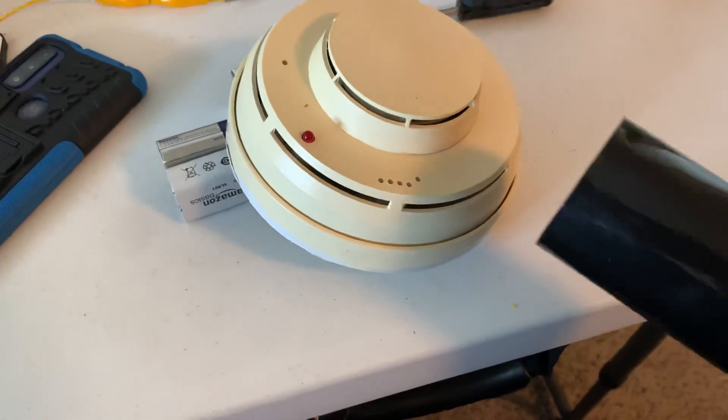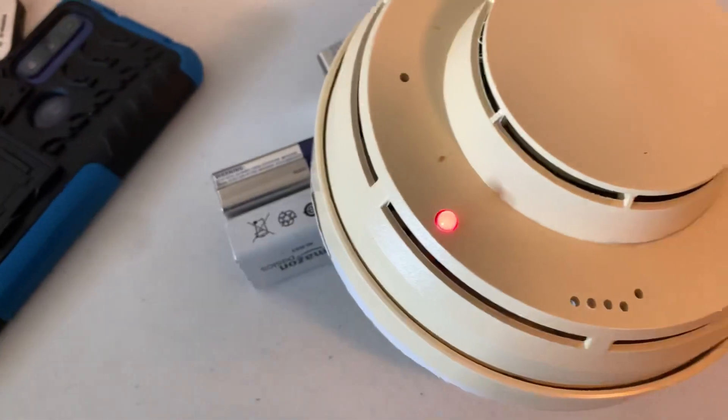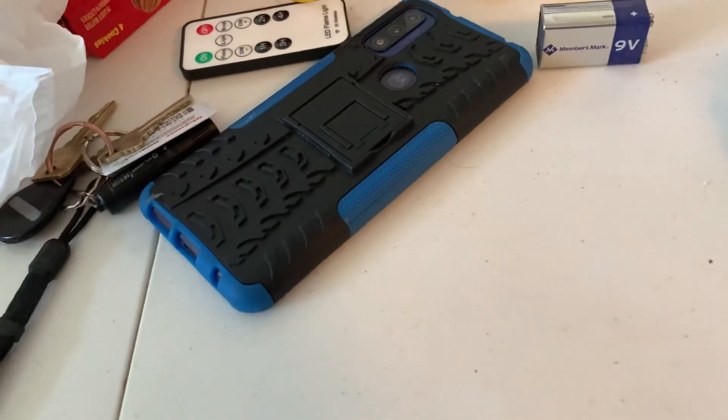Alright, I found my good smoke spray. It went right away. So now the question is — if I take the one away, leave it just at nine... I think that's just an alarm. Oh, it's not latching, because it just turned off. See if I can get it to do it. Well, now I can't get it to do it.